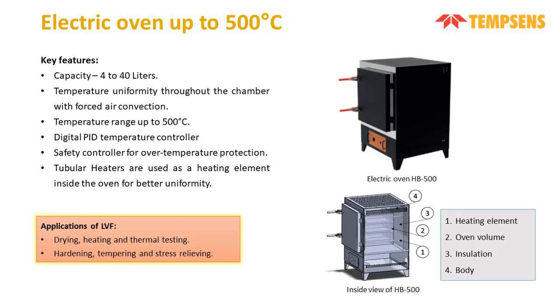Now coming to the last furnace, which is an oven in our laboratory furnace range. We have an electric oven for maintaining temperature from ambient to 500 degrees Celsius. The oven capacity is around 4 to 40 liters. The temperature is very uniform throughout the chamber. The maximum temperature is 500 degrees Celsius. It mainly uses the convection method for the transfer of heat, as all common ovens do. We use a tubular heater in the electric oven. Ovens are used for purposes like drying, heating, thermal testing, hardening, stress relieving, etc.